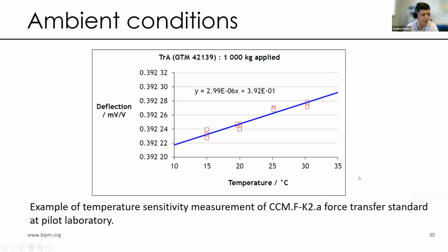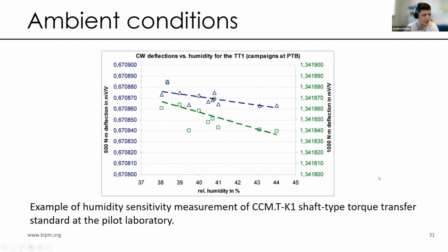We can see an example for a CCM.F-K2 comparison, and we can see that deflections are performed by the pilot laboratory at different temperature steps in degrees Celsius, from 15 up to 30 degrees, with steps of 5 degrees Celsius, and a straight line fitting procedure is performed, and so the sensitivity coefficient can be evaluated.